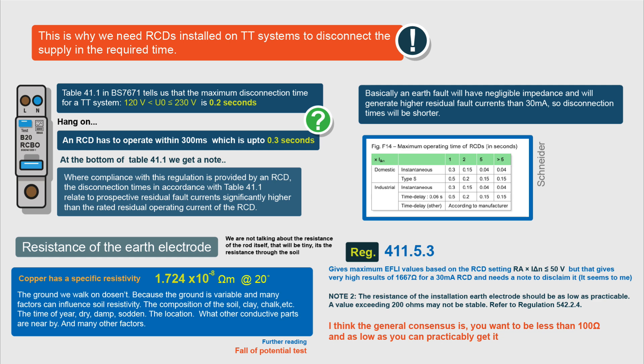As mentioned, the high earth fault loop impedance means that our disconnection times will not be met. This is why we have RCDs on TT systems. BS 7671 tells us that the maximum disconnection time for TT systems is 0.2 seconds, but when we're testing our RCD it can operate within 300 milliseconds, which is up to 0.3 seconds. That doesn't sound right, but if you look at table 41.1 there's a note: where compliance with this regulation is provided by an RCD, the disconnection times relate to prospective residual fault currents being significantly higher than the rated residual operating current of the RCD. You can see in this table — the higher the fault current, the quicker the device will operate.